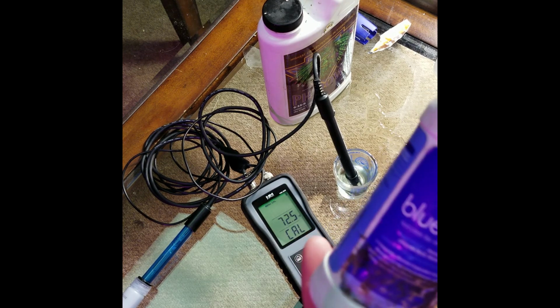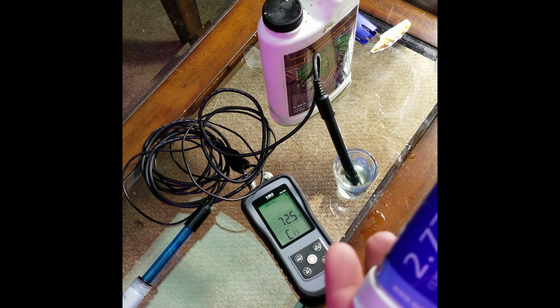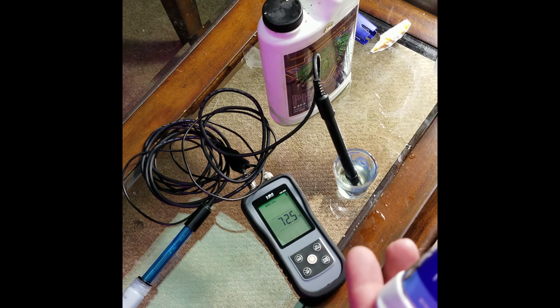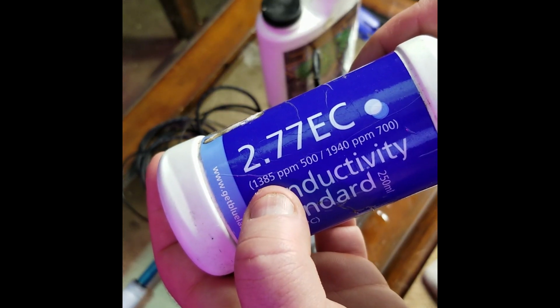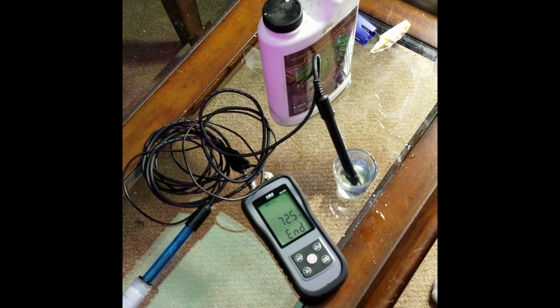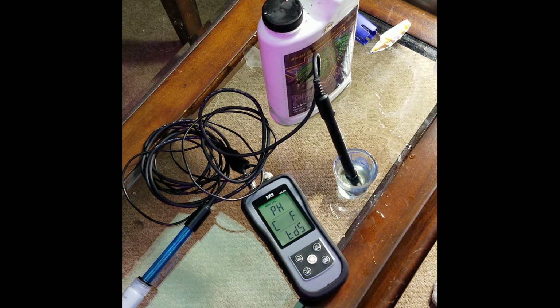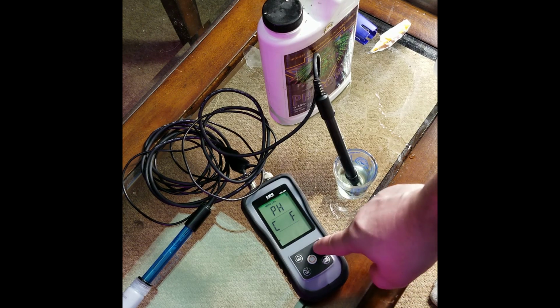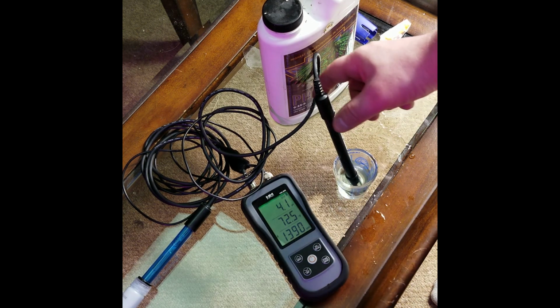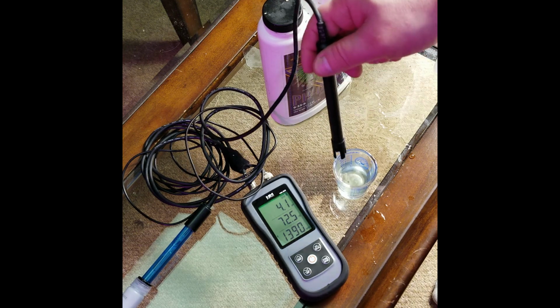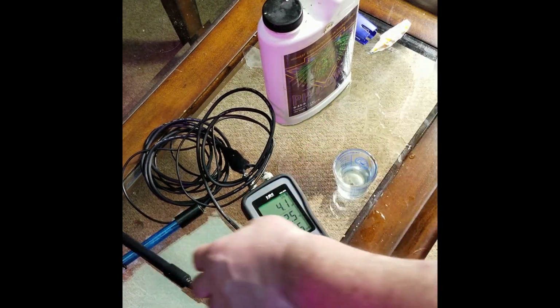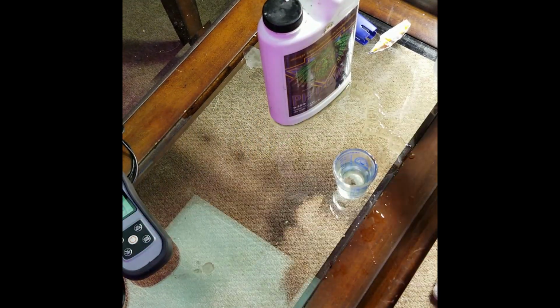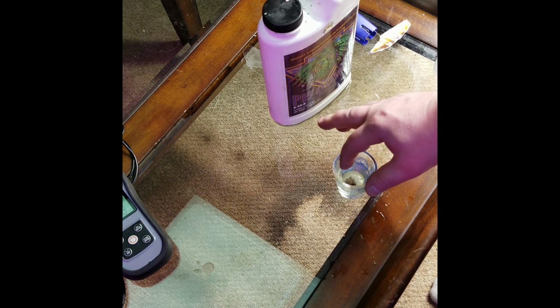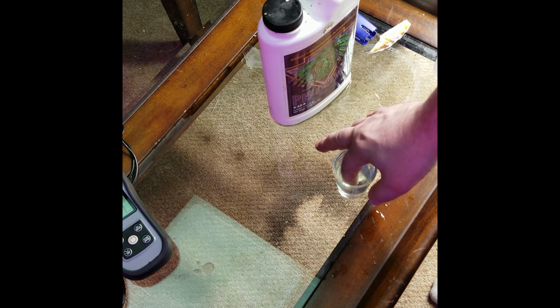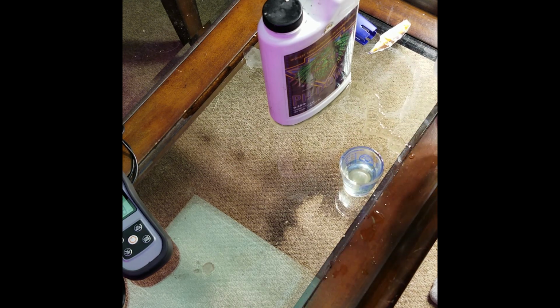And it'll calibrate it. Now this will never be exact, within like 10 or 20. It'll always be a little off, but it gets us very close to the ballpark. We know we're 1385 at the 500 scale. And that's it. So, we hit escape. See, it says 1390, so it's 5 points up. So this meter is perfectly calibrated, ready to go. Yeah, look at that chunk of crap from the top.